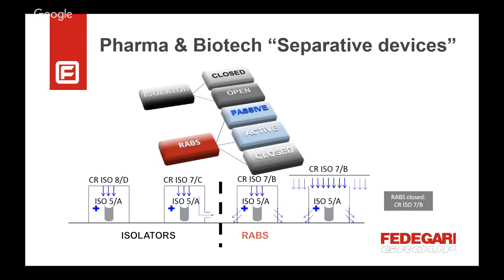But the isolator has other advantages. The main advantage is that it is environmentally friendly because you don't need all the background in a class B or ISO 7. Consider that a background of ISO 7 means that you should have a coverage of HEPA filter of about 30% of your ceiling, so a huge amount of air, and then also a big impact on the gowning of the people in terms of time. To gown for a sterile area, if you come from an unclassified area up to the sterile area, could take more than half an hour to go through all the steps. And then also the handling of all these sterile garments that have to be treated, maybe outsourced, the cost.